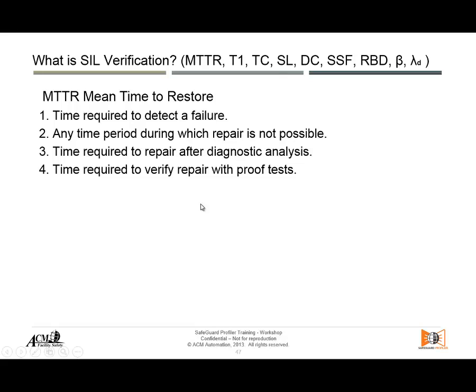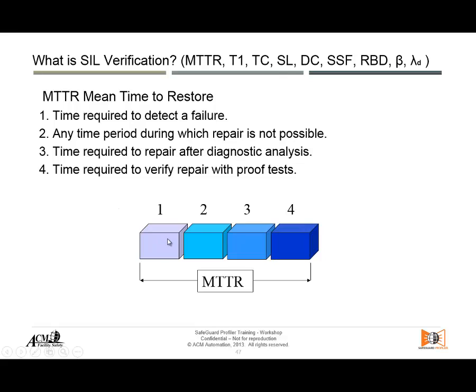Let's start with mean time to restoration. It is an accumulation of times. The mean time to restoration is important because that is the time you are going to be exposed to a probable demand — if the demand happens during that time, we are exposed because the safeguard is not going to work. Hopefully you will have your contingency in play, that other mitigating safeguard covering for the time you are restoring. Mean time to restore is usually given in hours.